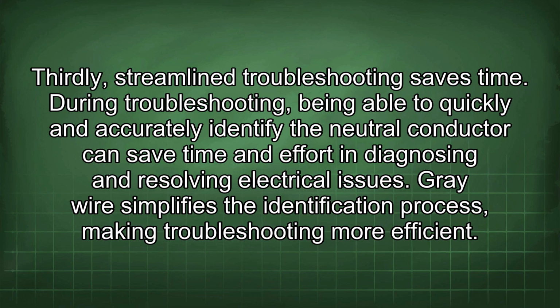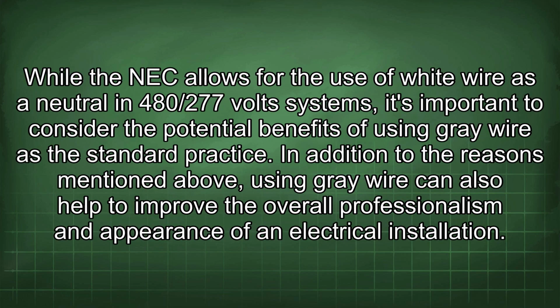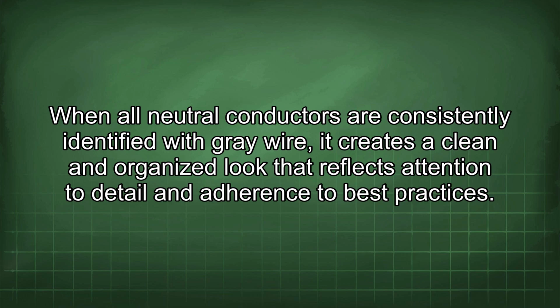During troubleshooting, being able to quickly and accurately identify the neutral conductor can save time and effort in diagnosing and resolving electrical issues. Grey wire simplifies the identification process, making troubleshooting more efficient. While the NEC allows for the use of white wire as a neutral in 480/277 volt systems, it's important to consider the potential benefits of using grey wire as the standard practice. In addition, using grey wire can also improve the overall professionalism and appearance of an electrical installation. When all neutral conductors are consistently identified with grey wire, it creates a clean and organized look that reflects attention to detail and adherence to best practices.